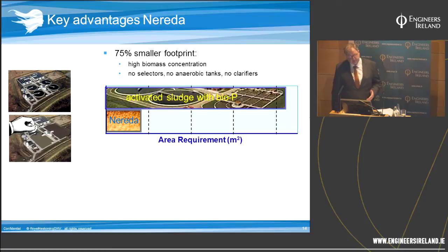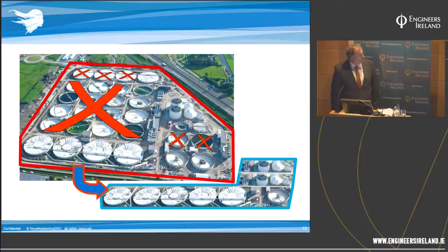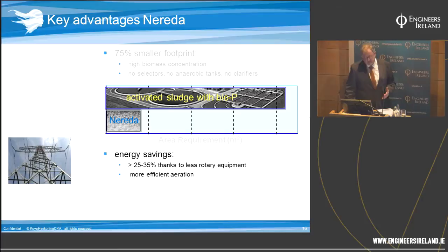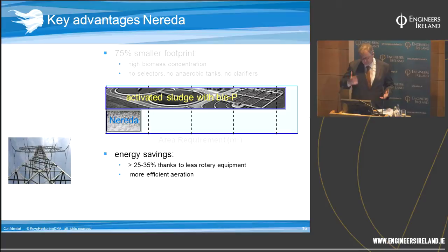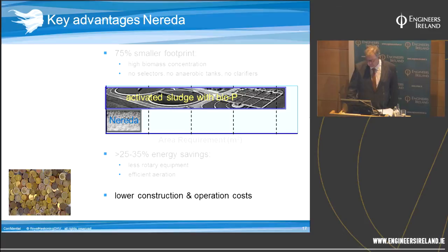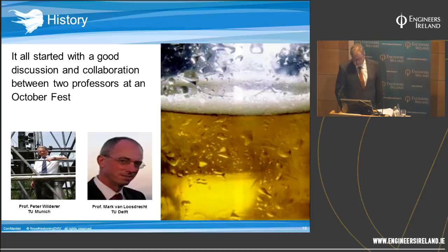In practical terms, the smaller footprint means the final clarifiers — the round tanks with the bridges — are eliminated. The upper drawing shows a traditional treatment plant with aeration basins and final clarifiers; in a Nereda design, those go away. This is illustrated by a well-known treatment plant near The Hague in the Netherlands. There are also energy savings due to two things: not pumping water around from one section to another means less rotary equipment, and oxygen transfer goes more efficiently in the reactor itself. Together, these lead to lower construction and operational costs.